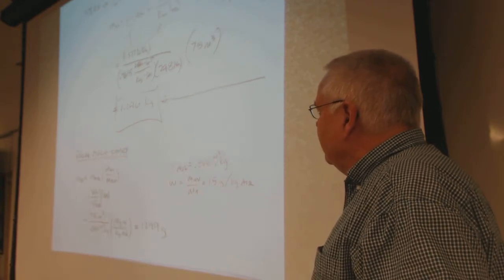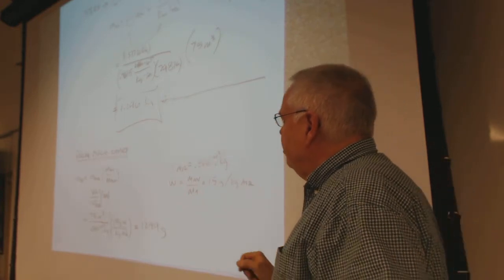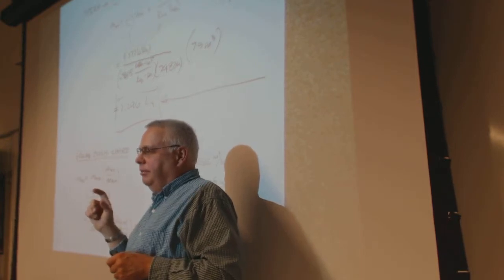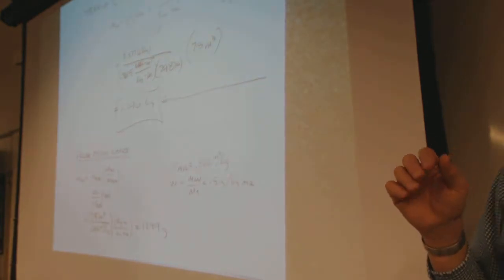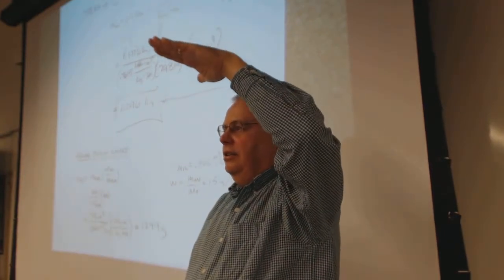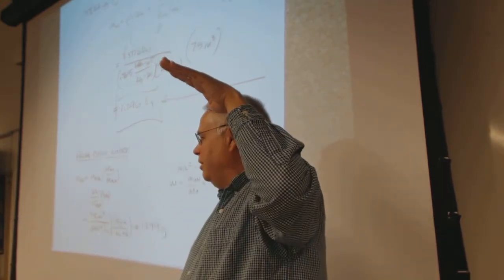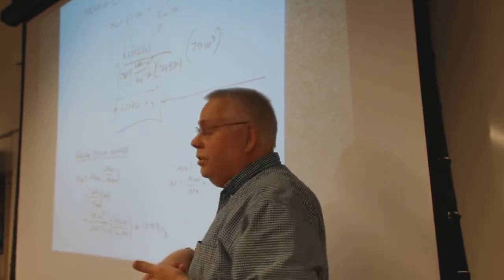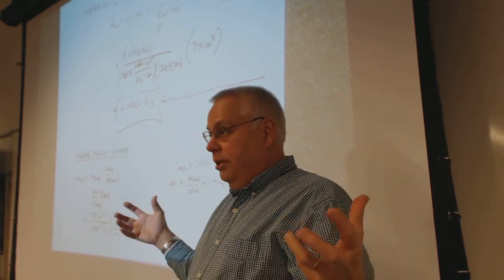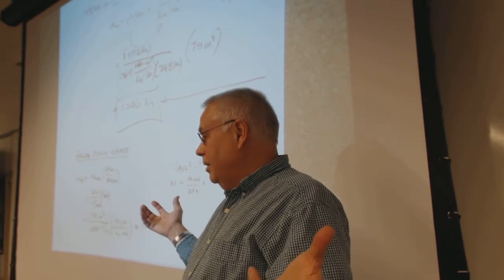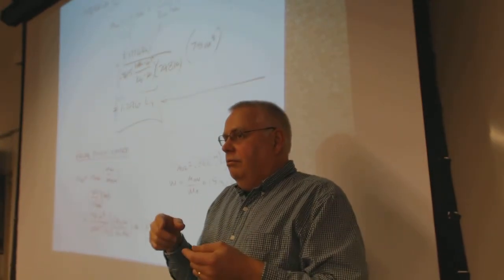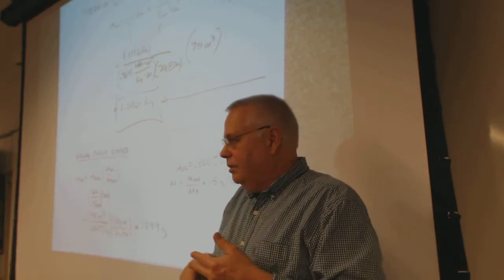Some of the things built into the psychrometric chart, there's different psychrometric charts for different altitudes, because the water vapor partial pressure is always going to be sort of a constant, how much water vapor you have, but the total pressure, total atmospheric pressure might get less and less, and so that chart starts sort of squished, things change in that chart depending on what total pressure is. So, I've seen these charts for sea level, which is like the one we're looking at. So, it's based on a total pressure of 101.325 kilopascal, and then you subtract from that the water vapor pressure, and then it fits into the air density thing. And I've seen them for 2,000 foot elevation, 4,000 foot, 6,000 foot, 8,000 foot.